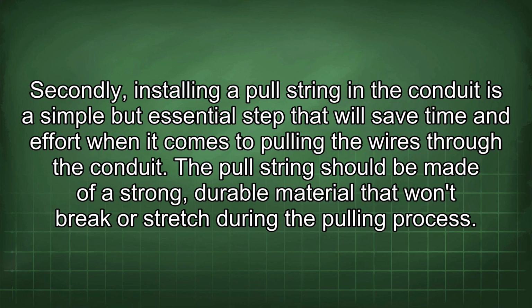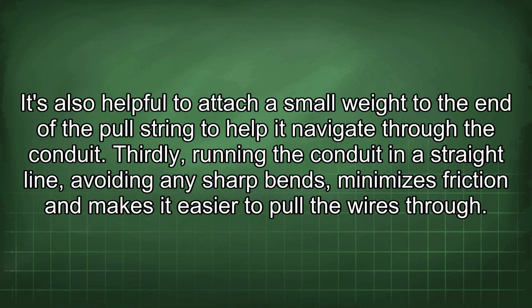The pull string should be made of a strong, durable material that will not break or stretch during the pulling process. It's also helpful to attach a small weight to the end of the pull string to help it navigate through the conduit. Thirdly, running the conduit in a straight line, avoiding any sharp bends, minimizes friction and makes it easier to pull the wires through.